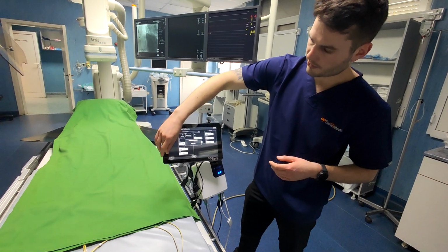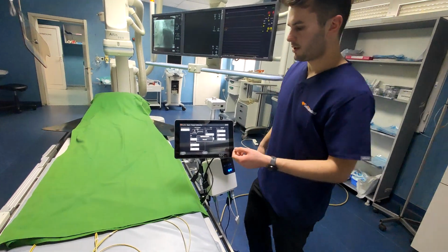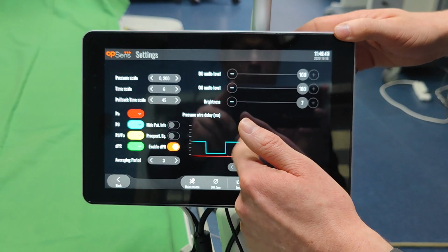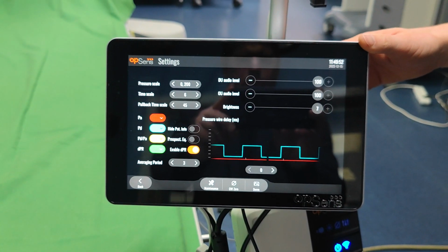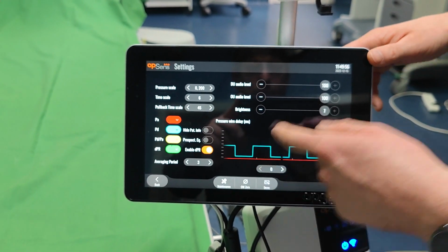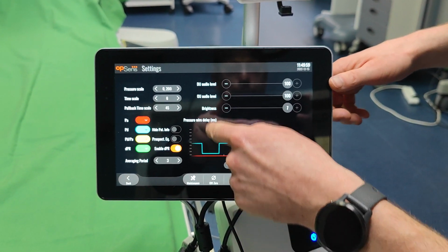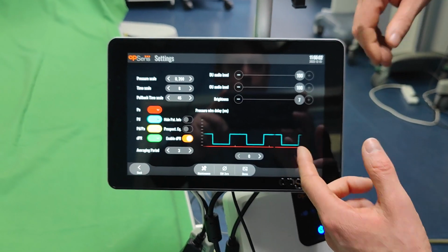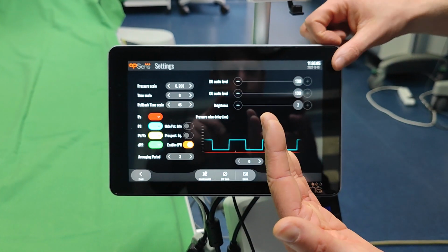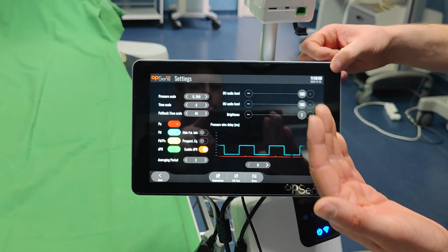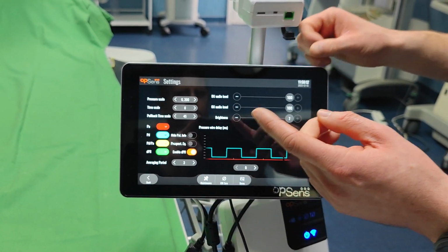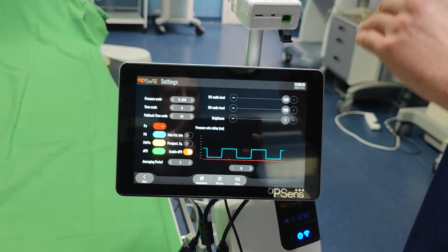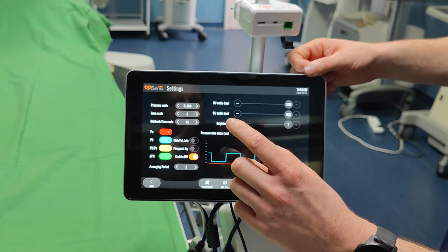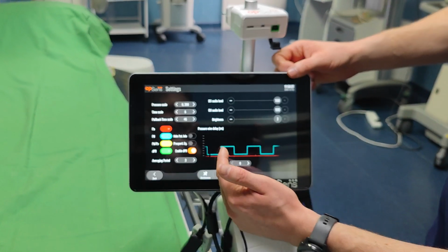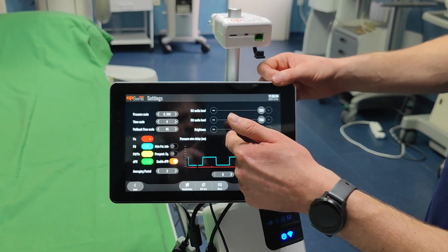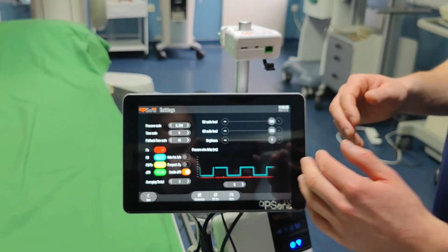Once that's all set up, the other thing you want to do is check your pressure wire delay. So when you're still plugged into theirs, you'll get two traces. The signal it sends out will also give you a similar appearance to the aortic trace. And the idea is you want these two to line up so that they're together on the screen. When you equalize, it should do that anyway to some degree, because the idea is it's bringing the pressure signals close. However, sometimes it can be off by a few milliseconds, in which case you're just looking for both of the lines to be superimposed over each other. So you should only see the one line essentially, and you just do that with this.